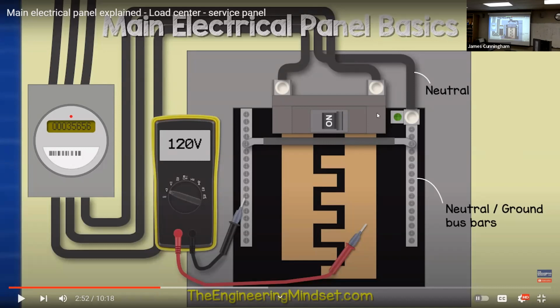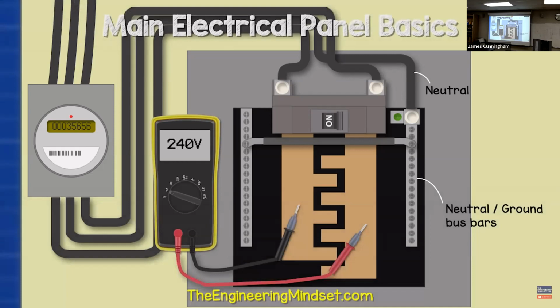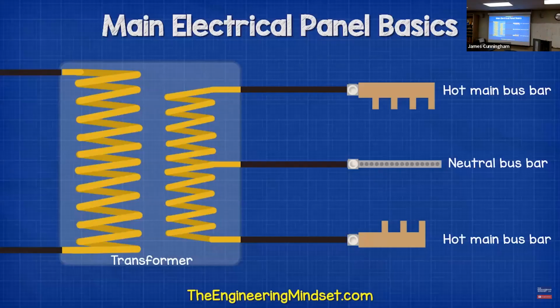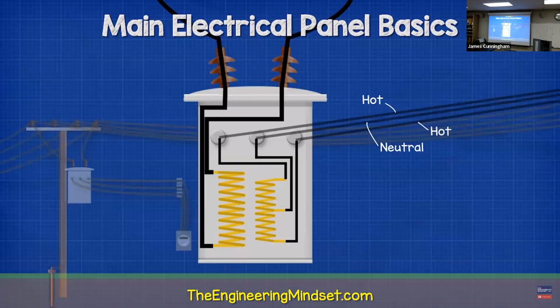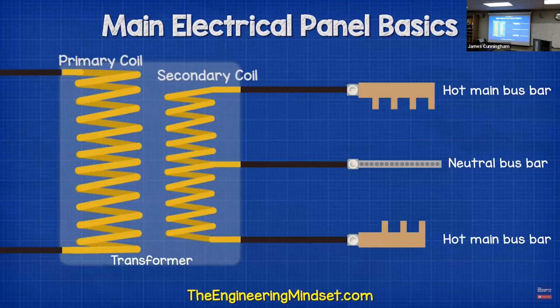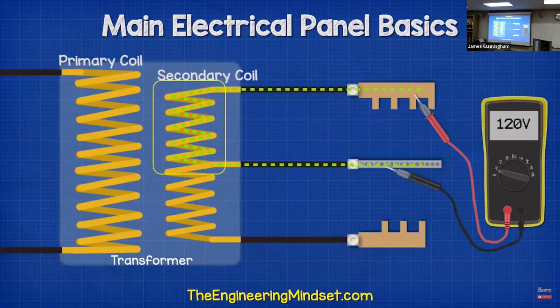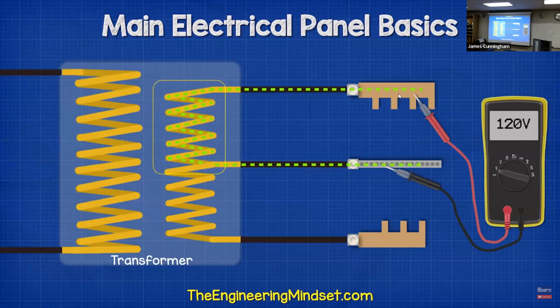You good? Yeah. Okay. Between the other bus bar and the neutral bar, we would again get a reading of around 120 volts. But if we connect the multimeter leads to the 2 bus bars, then we get a reading of double that, at around 240 volts. So why is that? What's happening here? When we look at how the transformer is connected to the main panel, we have the 2 hot bus bars connected to either end of the secondary coil in the transformer, and then the neutral bus bar connected to the center of the secondary coil. So when we connect across the bus bar and the neutral bar, we're only using half of the coil, so we are only picking up half the electrical voltage the transformer can provide. That way we get 120 volts.